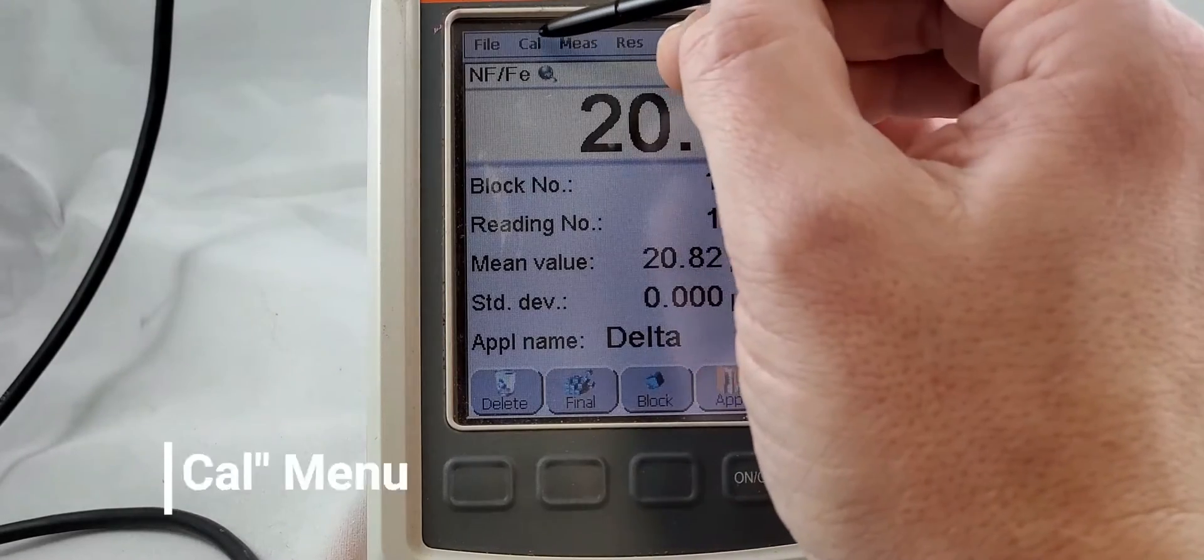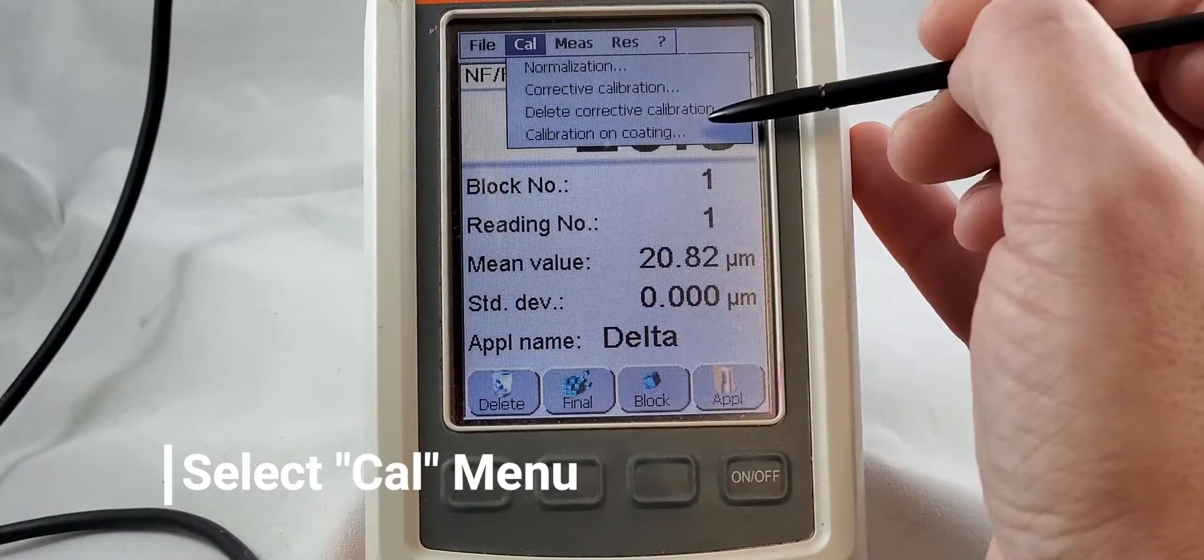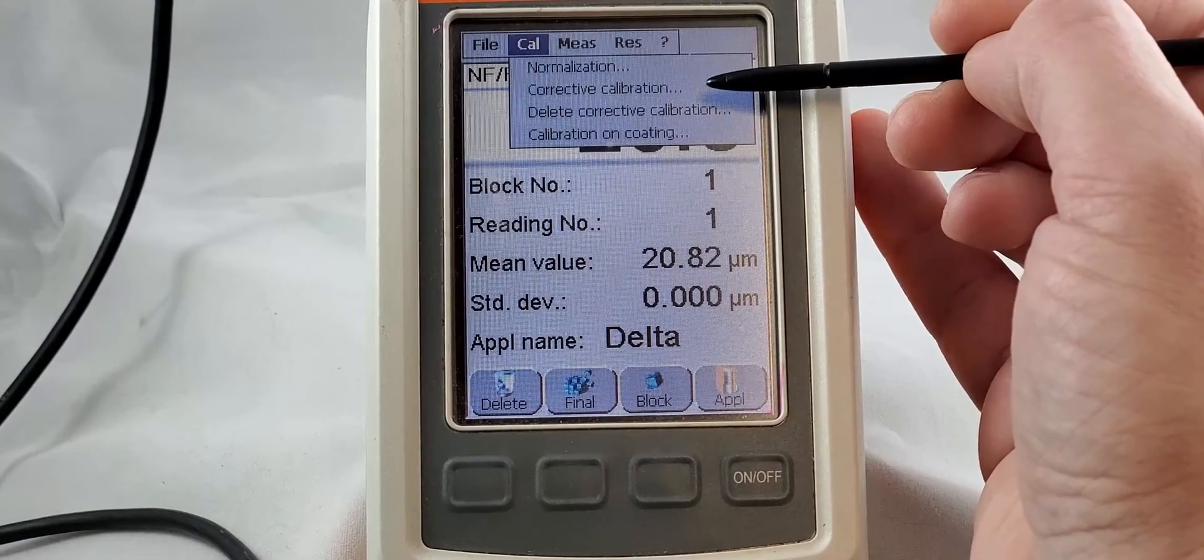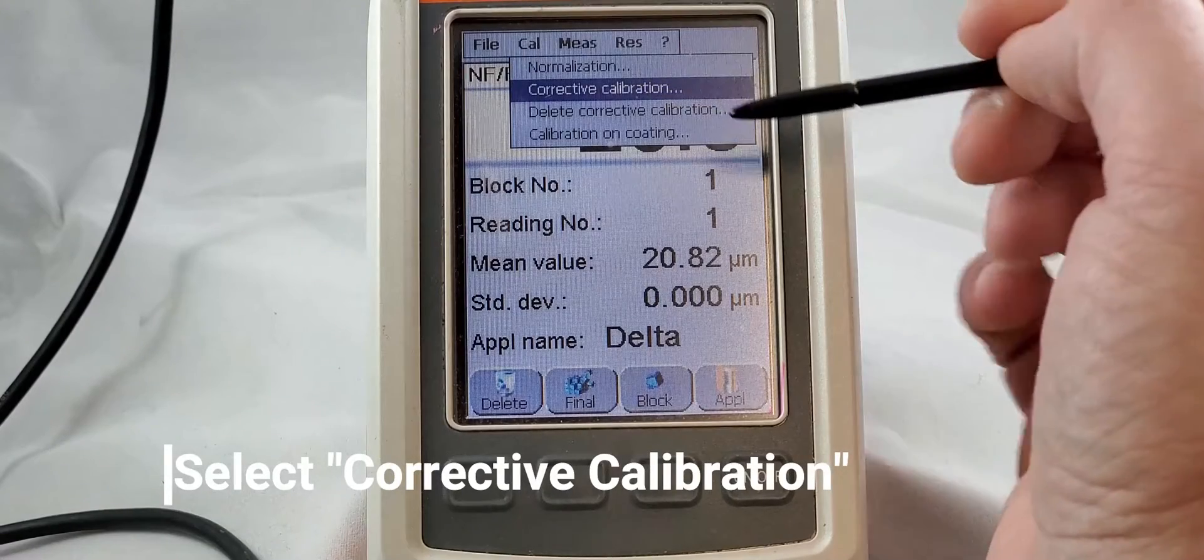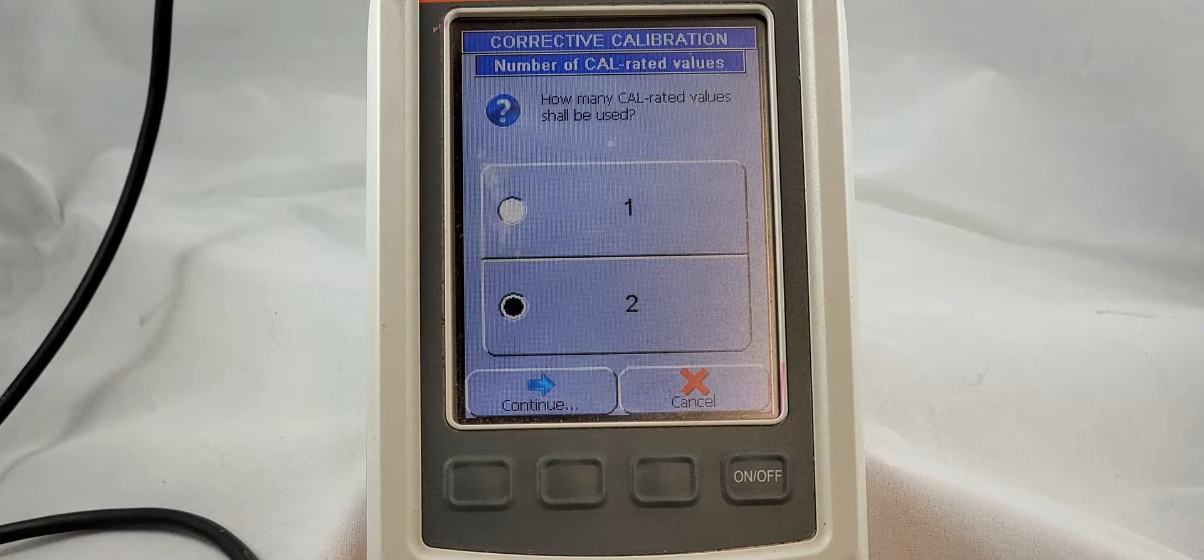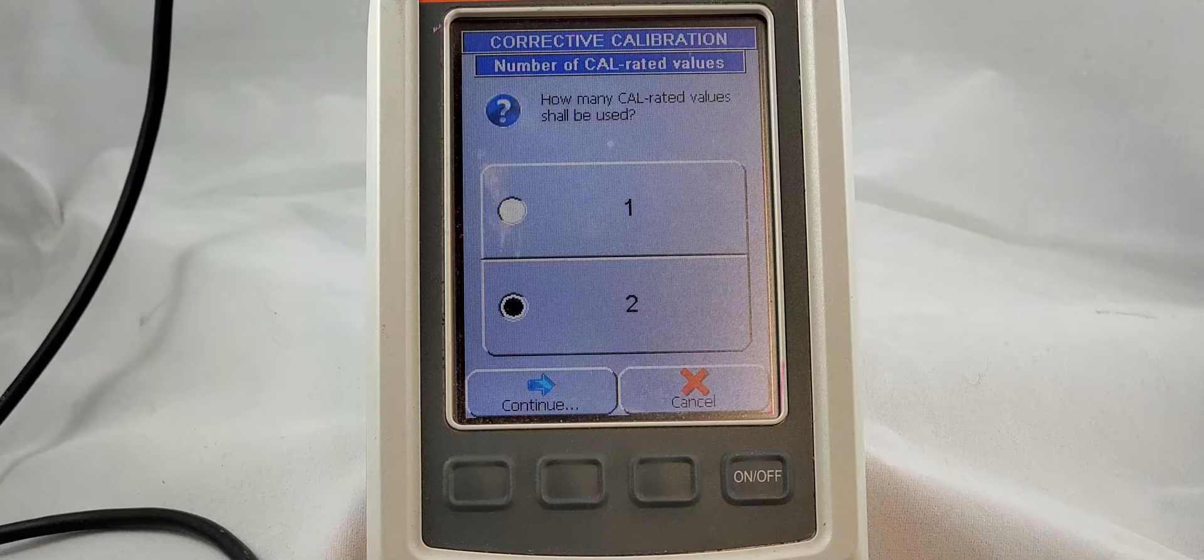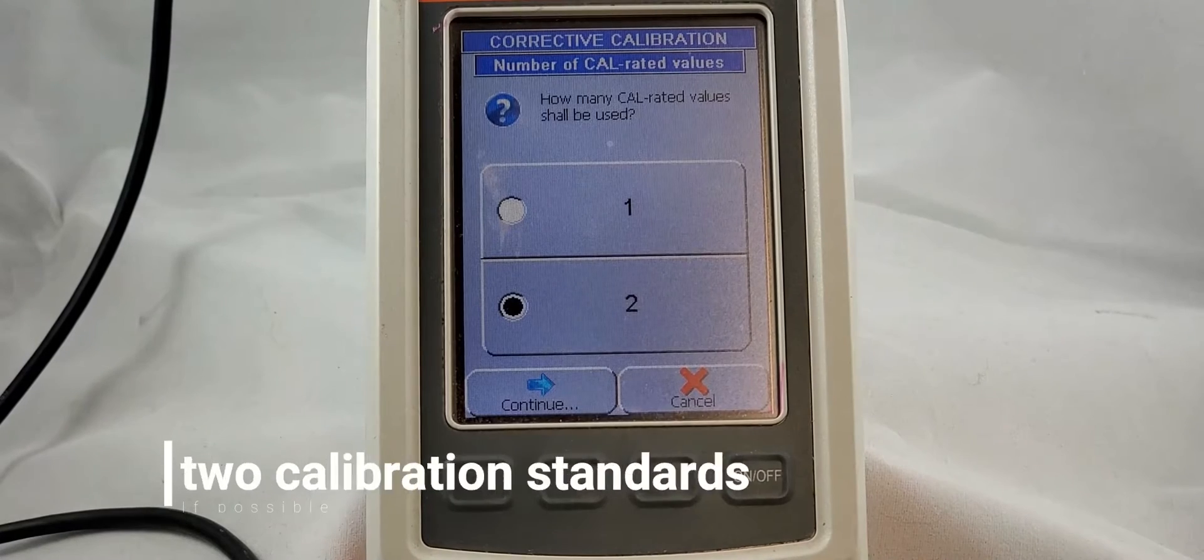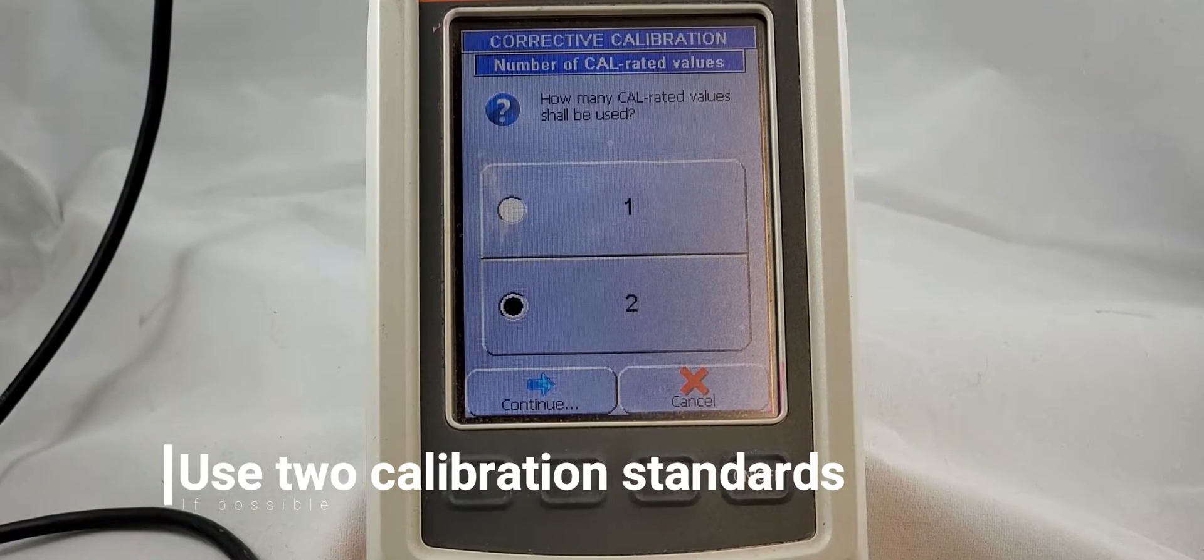Anyway, back to how to calibrate. We are going to go calibrate. Now we've got a bunch of different choices in here and here's where you want to always go when we're talking about calibrate and it is corrective calibration, because we want to correct the calibration that's already stored in the unit and true it up to either the coating that we're using or the substrate that we're using.